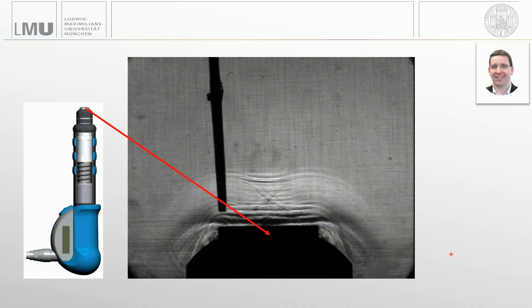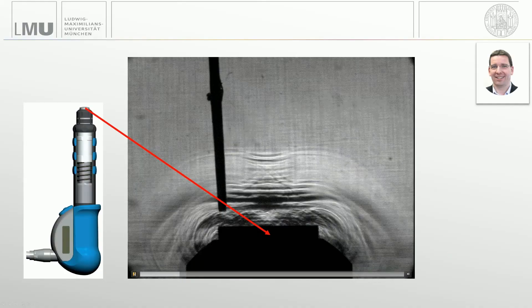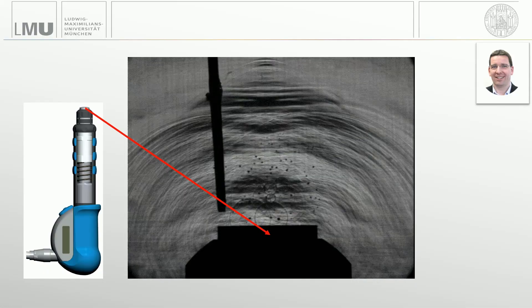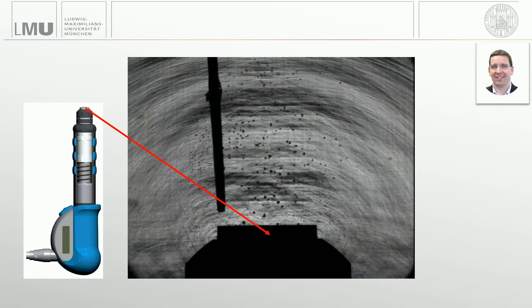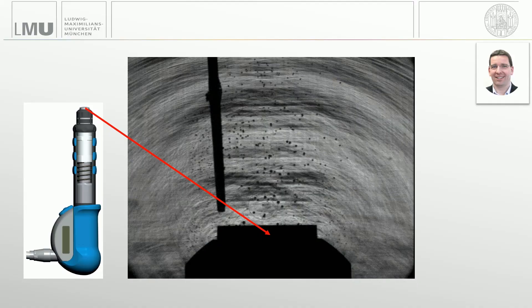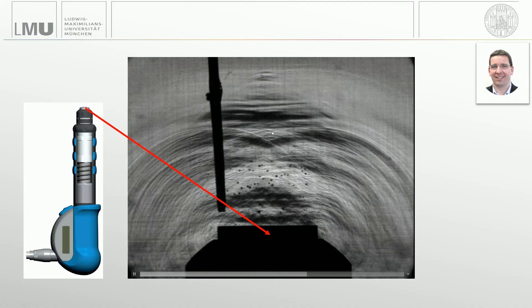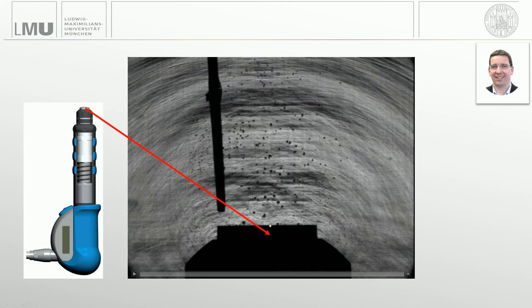Let's have a look at how such a shockwave actually develops. The technology we use for visualizing them is called shadow imaging. You shoot into water and with a high-speed camera you can take pictures showing how the wave is emitted from the applicator. You can see positive and negative pressure in black and white, and then cavitation bubbles appear approximately 2.5 cm above this applicator, which has a diameter of 15 mm.